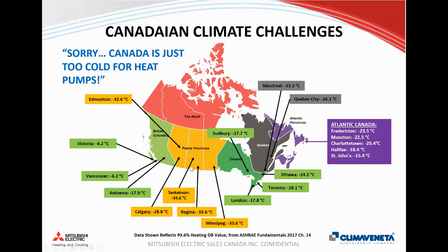But then if we look at the prairies, it gets very cold, routinely below -30 in the wintertime. So obviously that's below the cutout of -15 degrees Celsius. But again, if you look at the number of bin hours where you actually are seeing these colder temperatures, according to climate data, which we'll look at on the next slide, you'll see that it's not really as bad as it sounds. So typically, if your design temperature is below -15 or -20, you'll need an auxiliary heat source anyway, and that's okay because in a low carbon economy, it's more about using energy in the best way possible: use the heat pump when it makes sense to, and use auxiliary heat, either an electric or a gas boiler, when it's feasible to do so.